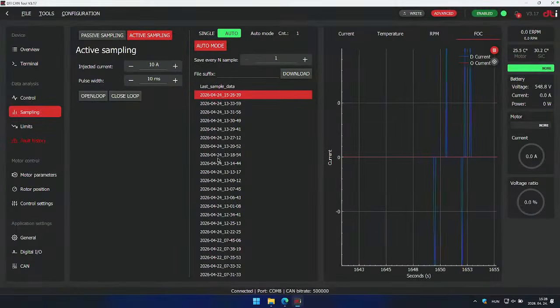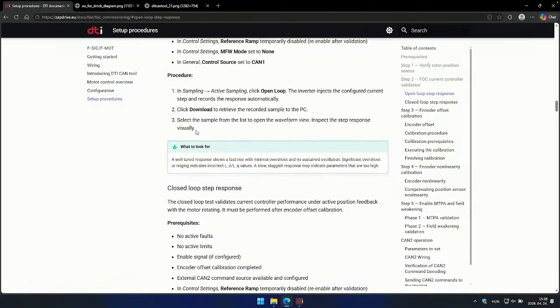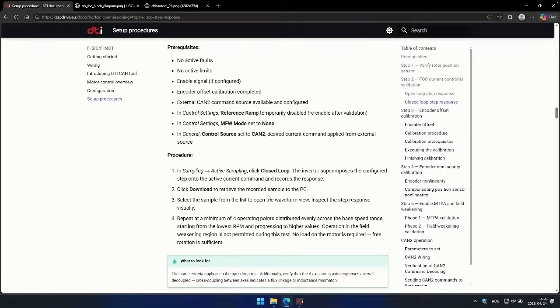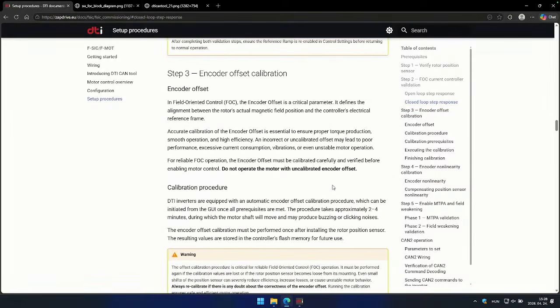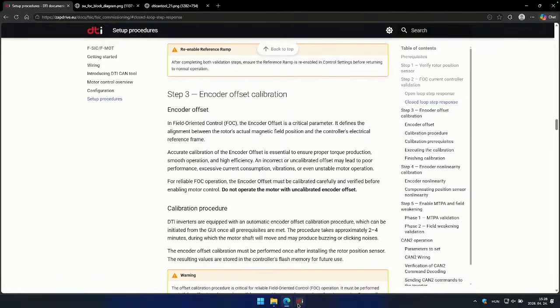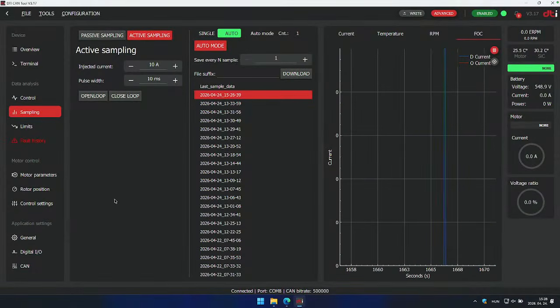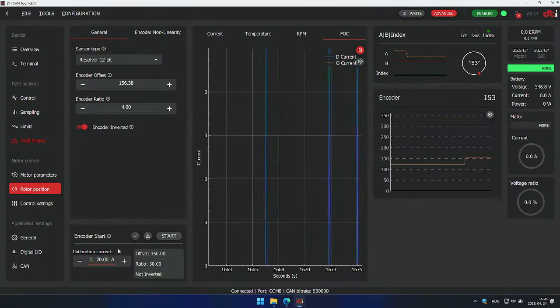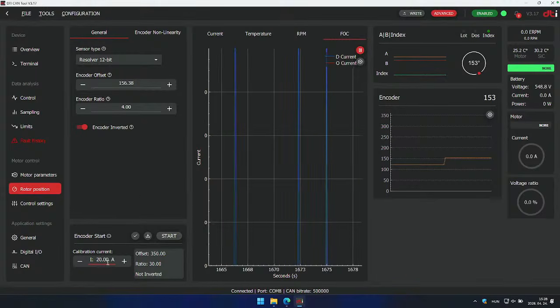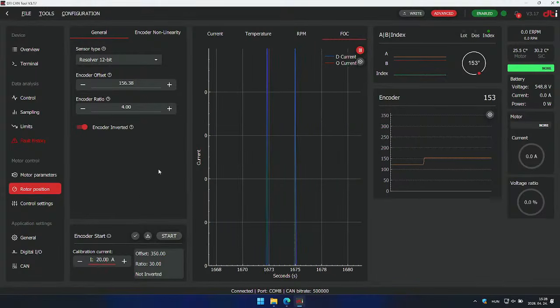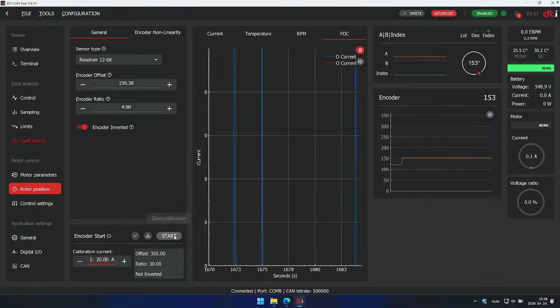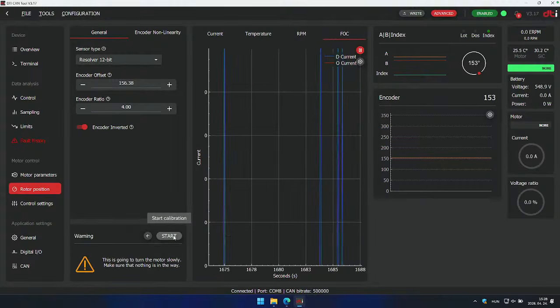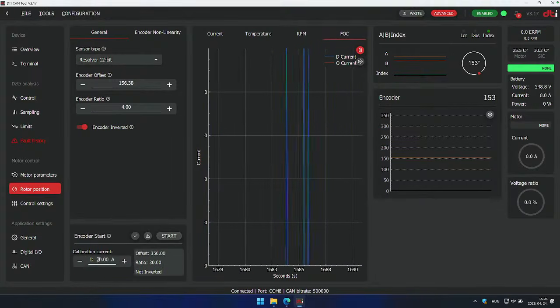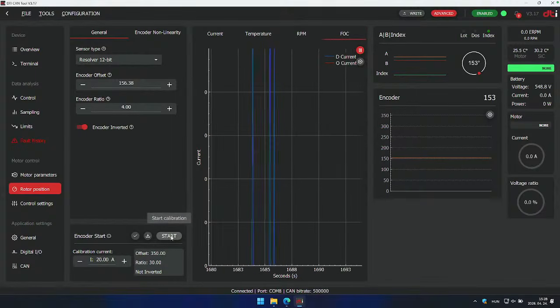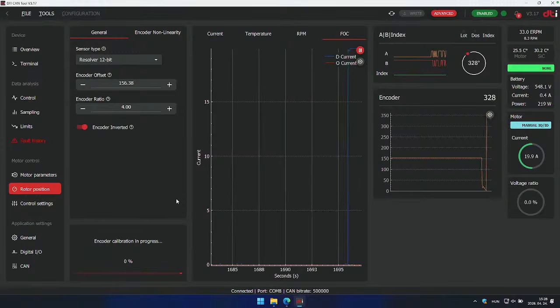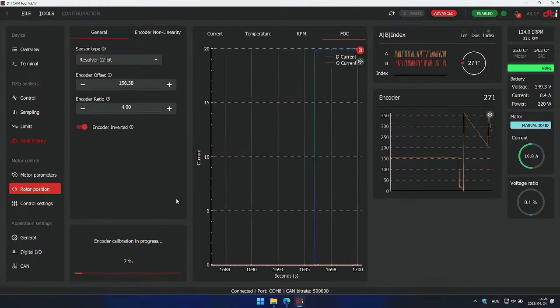The next thing we have to do is not the closed loop step, it is the encoder offset calibration. We know that electrically the current controller works fine, so it is safe to calibrate the encoders. Right now it's resolvers, because we need the encoder offset for the motor control algorithm. We have an automatic calibration procedure, so you have to type 10 or 20 amps of current, really enough for the DTI F mode. Press the start button, and the calibration procedure starts.